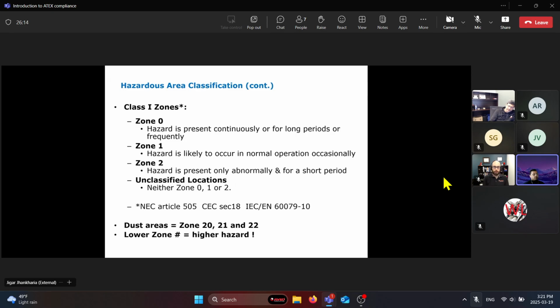So any product that is certified for Zone 0 can be installed in Zone 1 and Zone 2. Any product certified for Zone 1 can be installed in Zone 1 and Zone 2. Products certified for Zone 2 can only be installed in Zone 2. Similarly, Division 1 products can be installed in Zone 0 and Division 2 and Zone 1. But again, that depends on the method of protection.